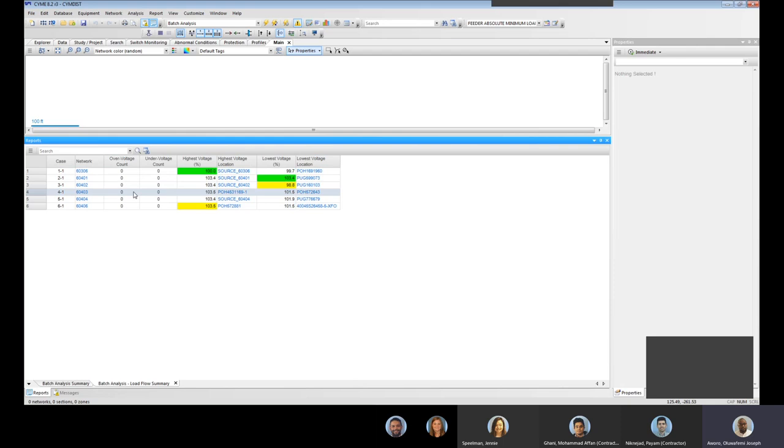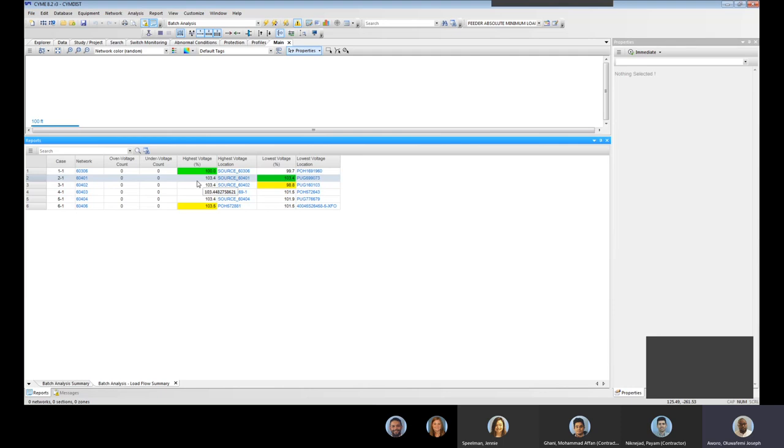So you come down at the results tab, the second tab is the result we're actually interested in. And if I shift this up, so these are the six feeders: the case, the networks, the over voltage, under voltage counts, highest voltage and the location, the lowest voltage and location. So basically what this means is, since we are dealing with a minimum load day, we're going to be interested only in the high voltage. So in most cases I will normally want to export this to Excel.